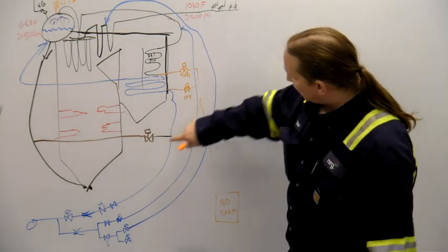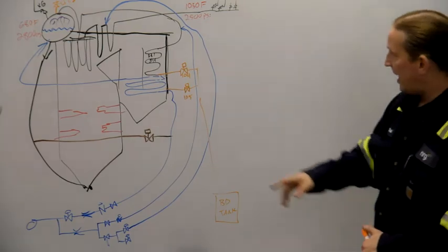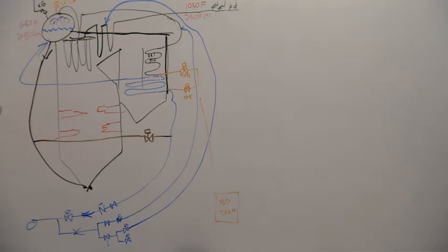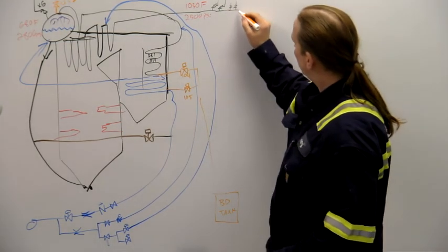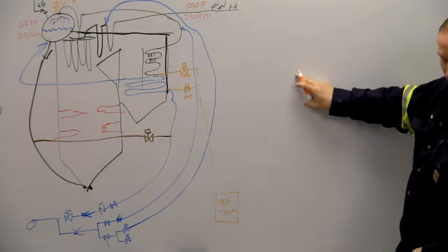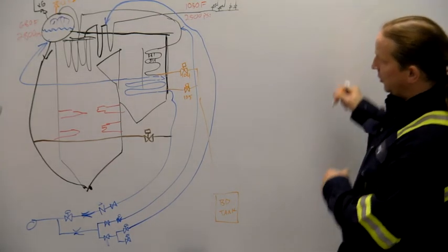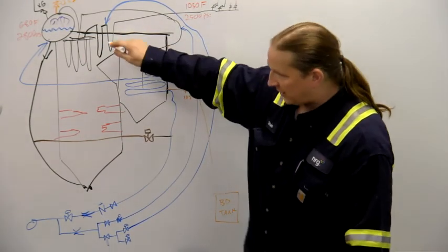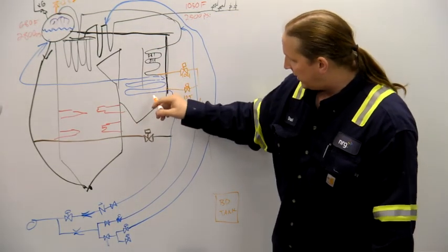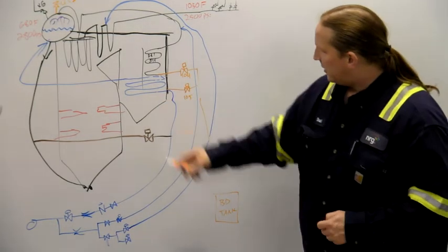And similar to the recirc valve, this is all about keeping flow through the system. It's all about making sure that the pipes just have steam to flow through, right? Similarly, down at the turbine, we've got a drain on the main steam header. That's giving the steam somewhere to go, so that all these secondary and tertiary sections have steam flowing through them, or else you have the same overheating risk that you do in the economizer.